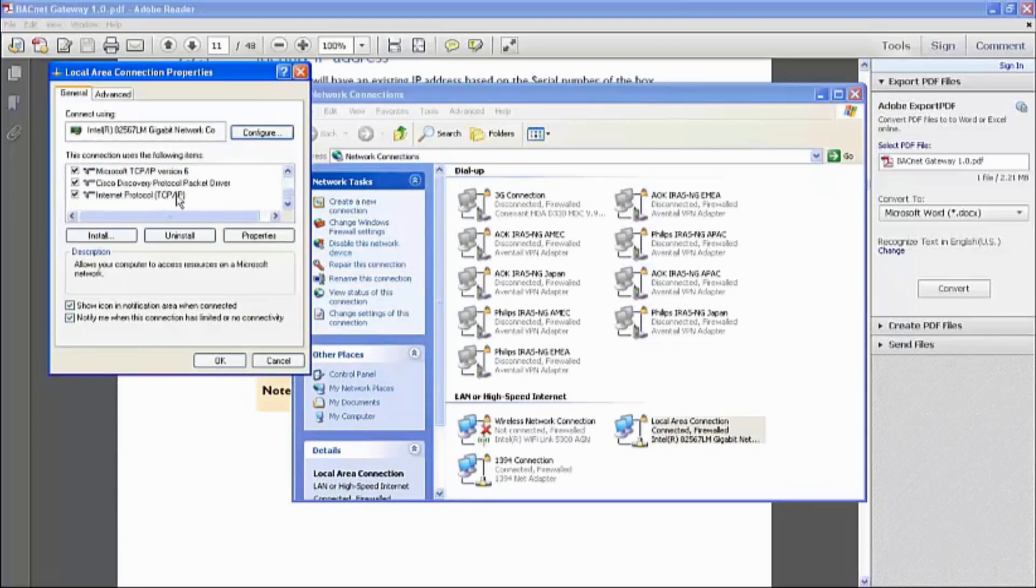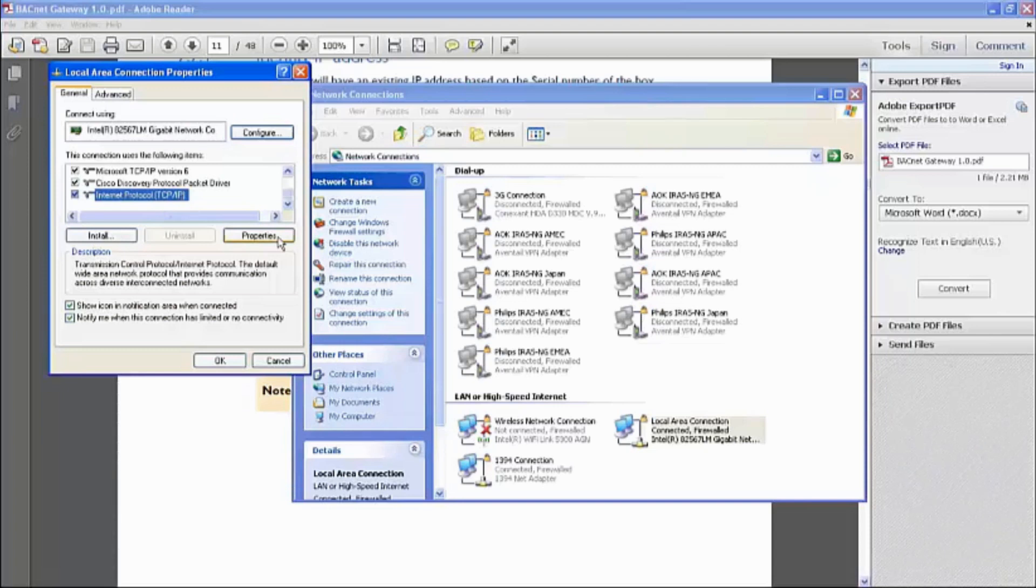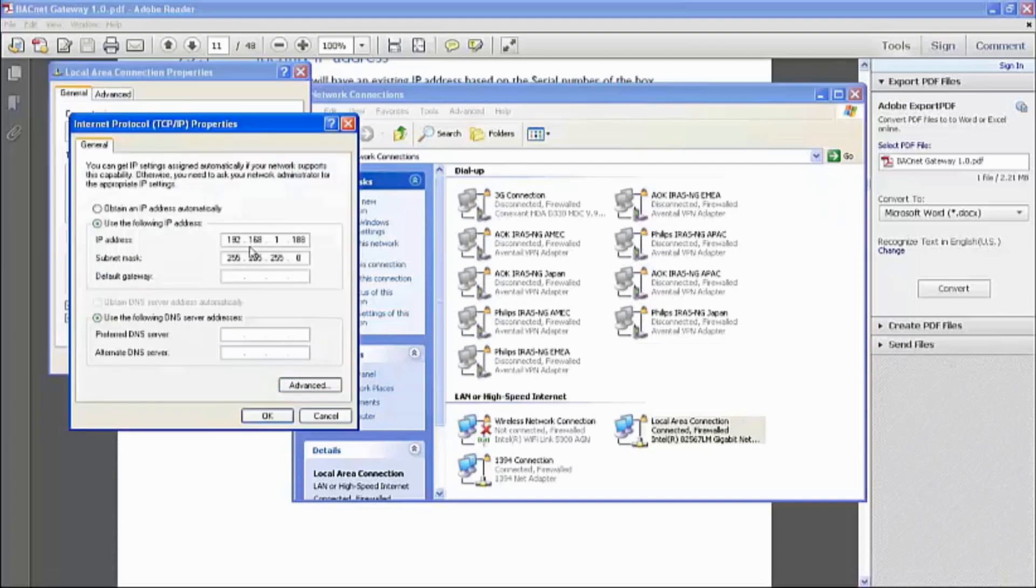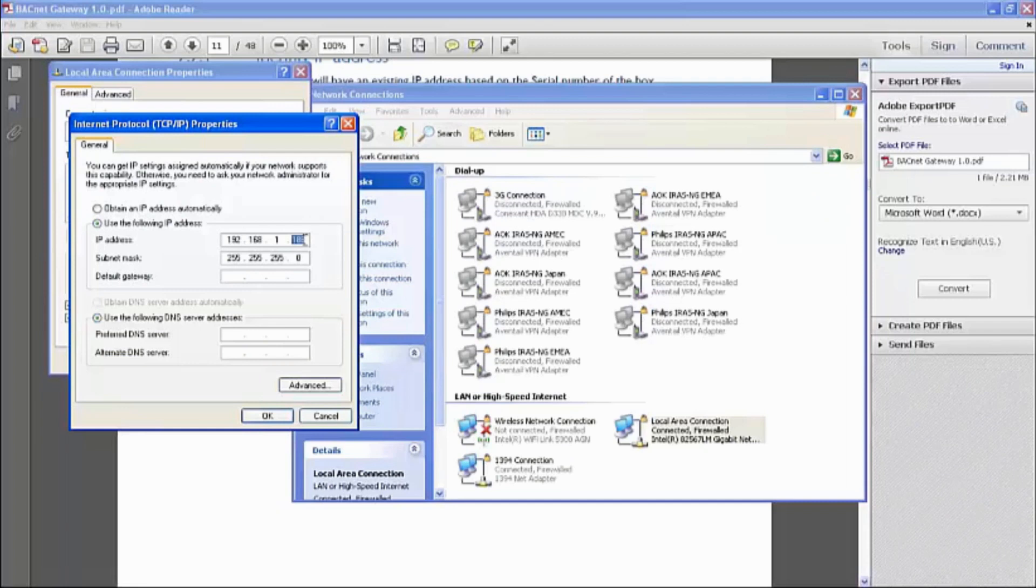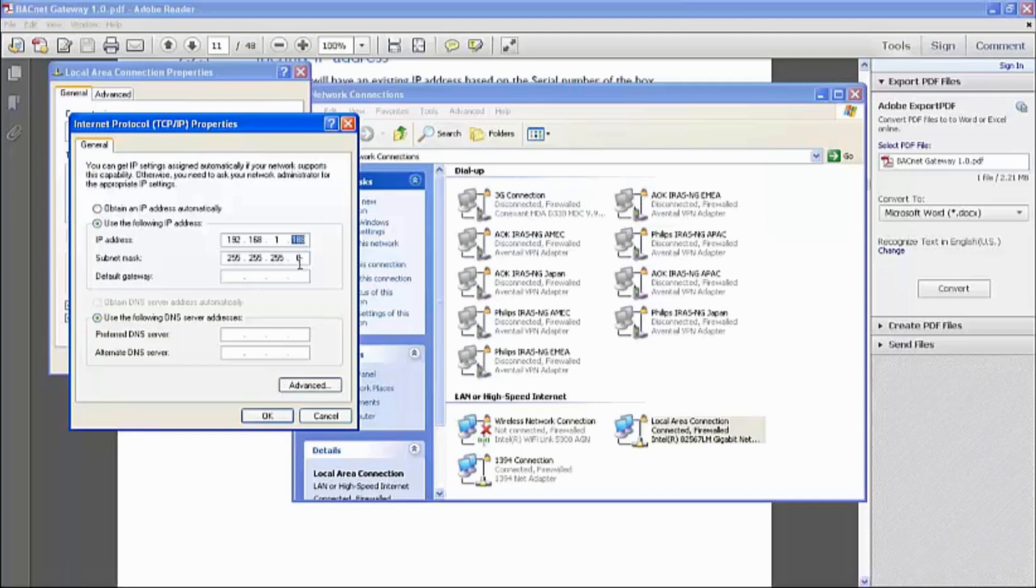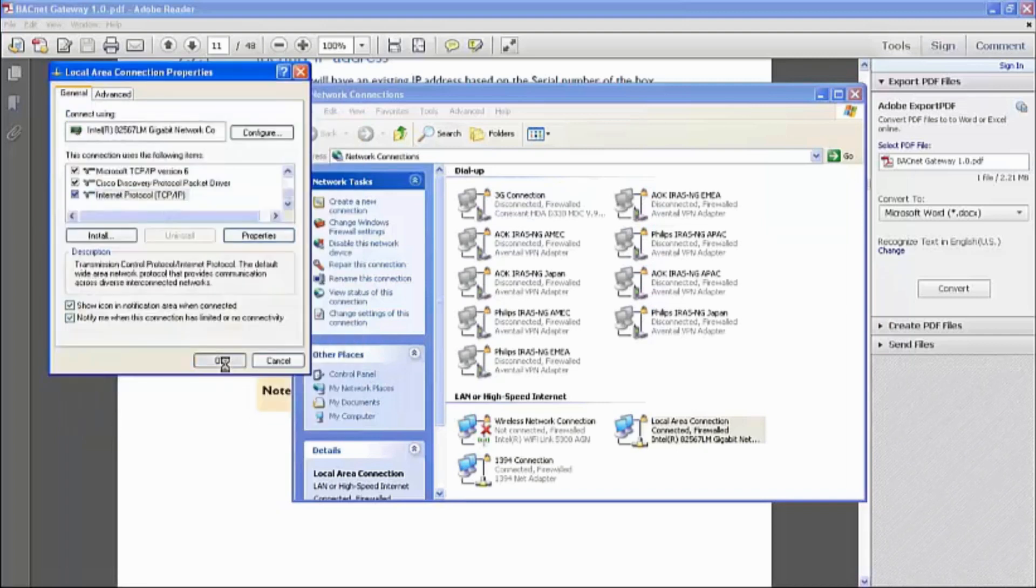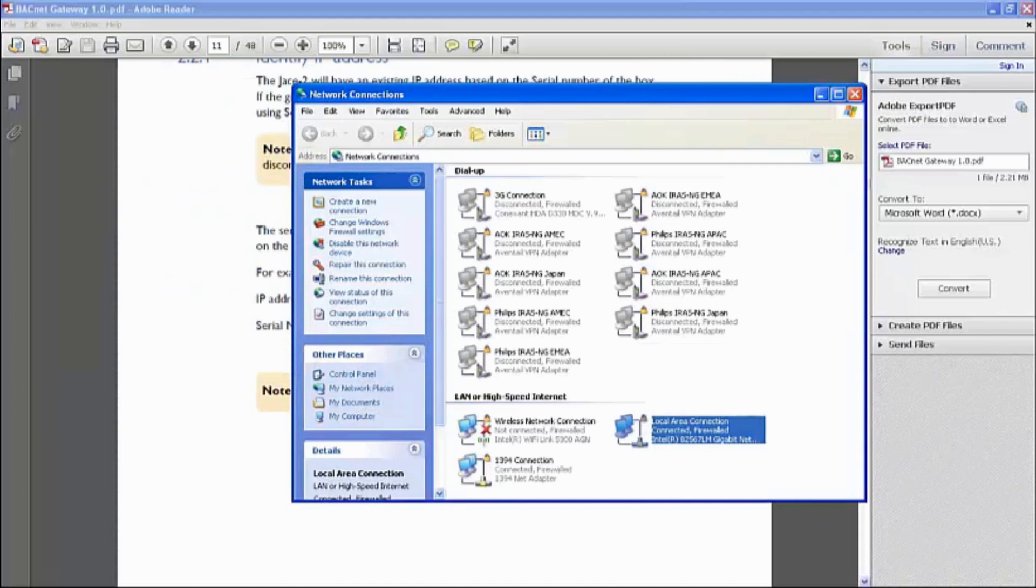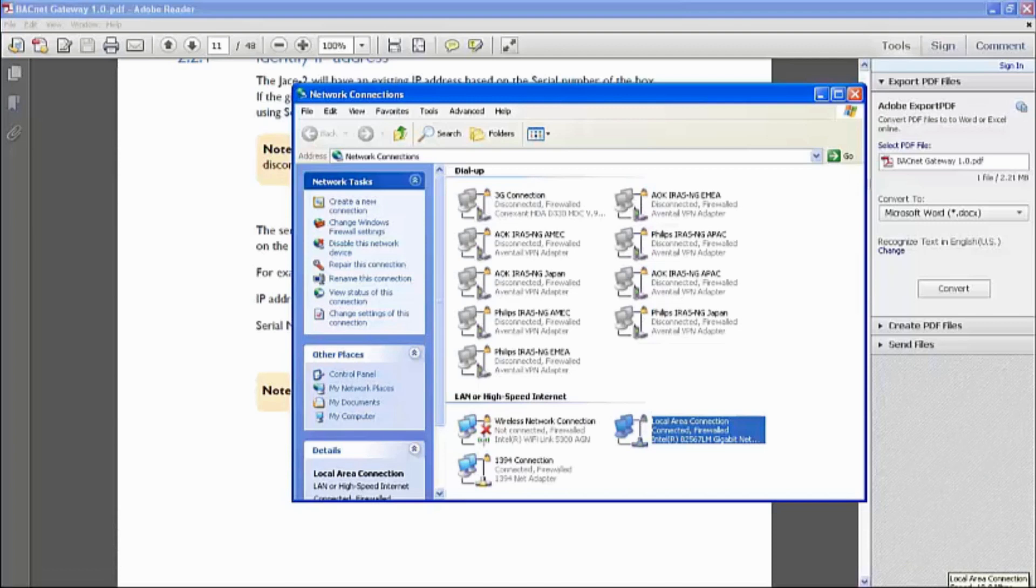Of course, Windows 7 will be IPv4, TCP IPv4. Mine is still on XP. We can change the IP address. Of course, the last octet has to be different from the JACE unit. It cannot be 123 because you will not be able to communicate. With that set up, click OK and OK.